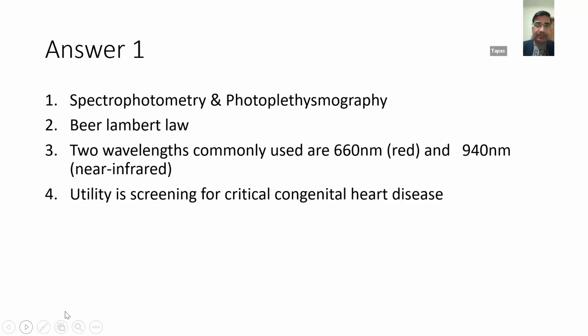In the pulse oximeter probe, you must have seen one side has a red light that is fluctuating, and the other side has the detector. This light is actually two lights of two different wavelengths. First is the red spectrum, with a wavelength of about 600 to 750 nanometer, and the other is the infrared light, which is not visible to our naked eyes, with a wavelength of about 700 to 1300 nanometer. Normally oxyhemoglobin absorbs more of the infrared light, and deoxyhemoglobin absorbs the red wavelength of light.